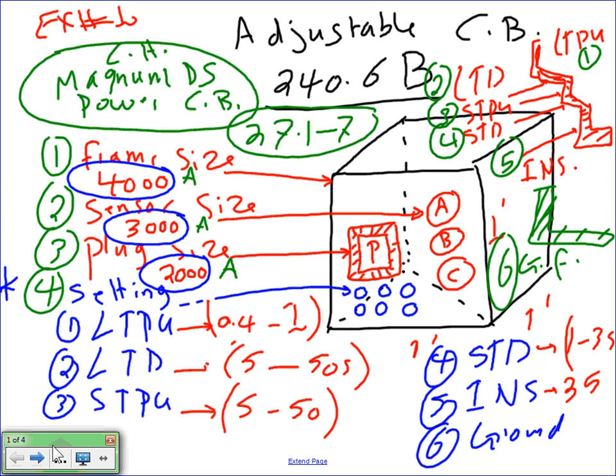If you have a Magnum DS power circuit breaker, Square D, you're going to have four things about every power circuit breaker, guys. And we talked about this one. You're going to have the frame size, 4,000 amp in this case. You have the sensor size. These are the CT donuts, 3,000 amp. You have the plug size. This is a tiny electronic piece of equipment that you plug right into the face of the circuit breaker. This could be 2,000 amps. And the bottom, the fourth, is the settings: long time pickup, short time pickup, long time delay, short time delay, and instantaneous, plus the ground.